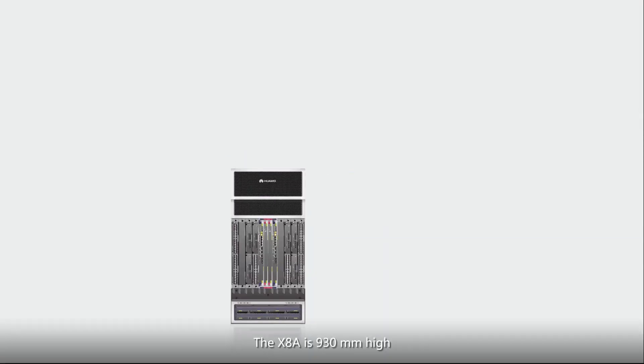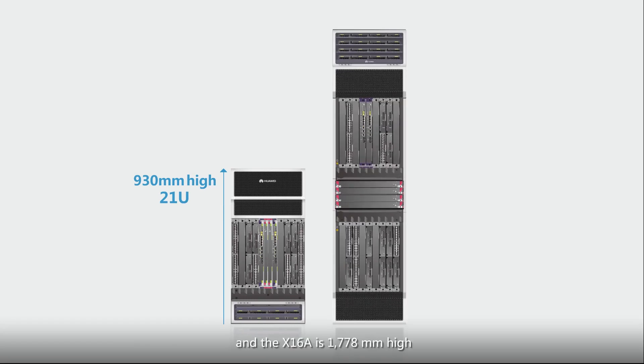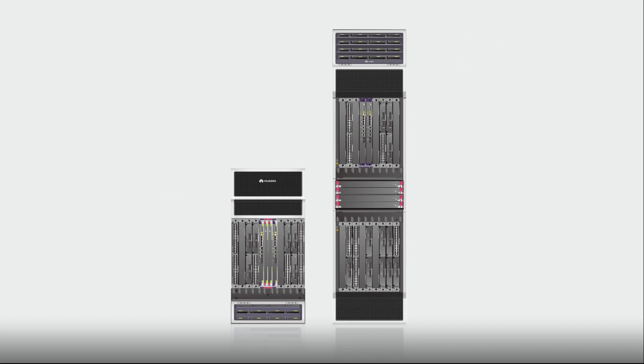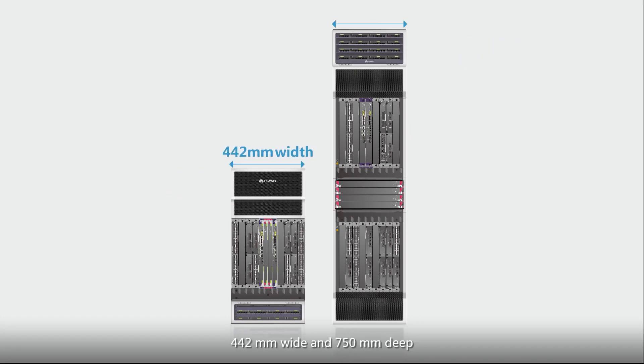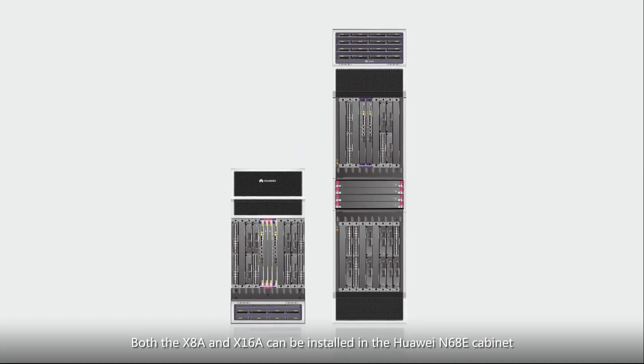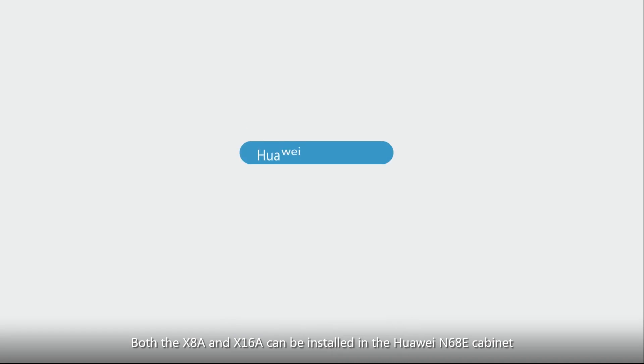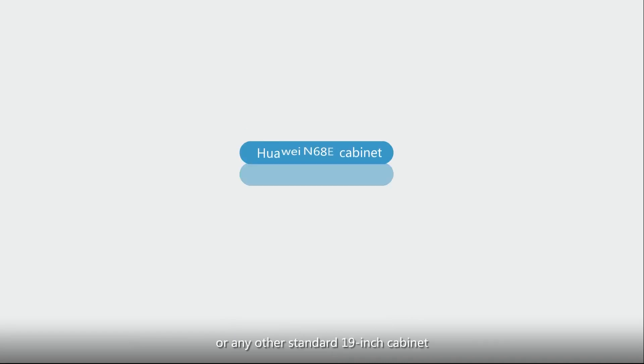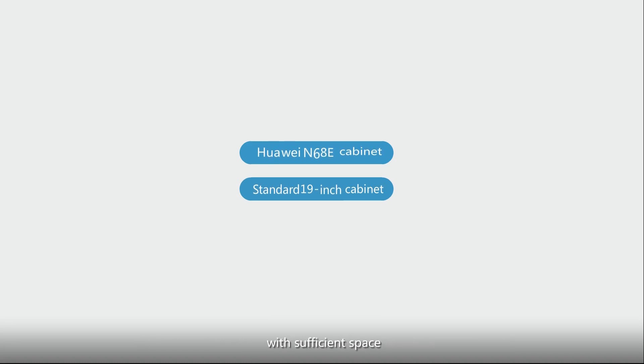The X8A is 930mm high and the X16A is 1778mm high. The X8A and X16A are both 442mm wide and 750mm deep. Both the X8A and X16A can be installed in the Huawei N68E cabinet or any other standard 19-inch cabinet with sufficient space.